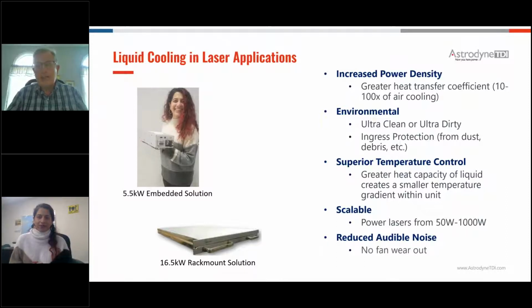The heat capacity of liquid creates a smaller temperature gradient within the unit. That generally means your components can run cooler for a given amount of power. One of the leading things that can improve your reliability is temperature, so if you can keep your temperature down, your reliability will improve. Liquid cooling, we've found, is one of the great aids in supporting a longer life of the power supply.